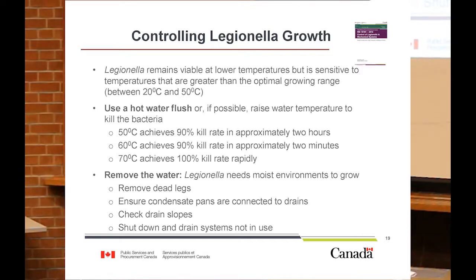And then at 70 degrees Celsius, if we are doing a hot water flush, we're going to get a rapid kill rate on the bacteria at 100%. So we do have flushing time minimum requirements where we'll raise the temperature of our storage medium to 70 degrees Celsius and then progressively flush through the system for 20 minutes at each fixture.